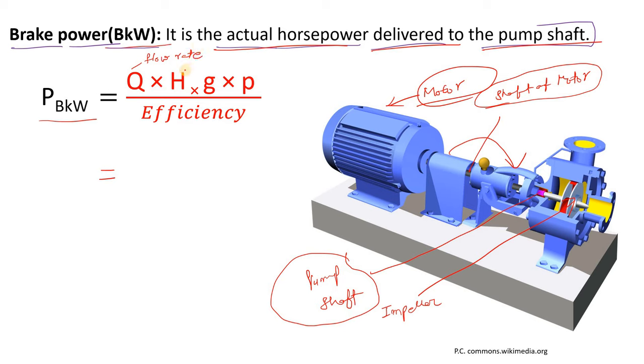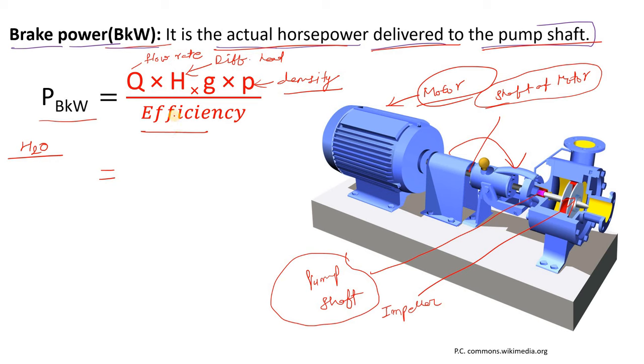Q is the flow rate of the liquid — let's suppose water — which you have to pump from one location to another. H is the differential head. G is the acceleration due to gravity. Rho (ρ) is the density of the liquid you are pumping. Divided by efficiency — if you know it from the vendor's data sheet, use it; otherwise you can assume 0.6.